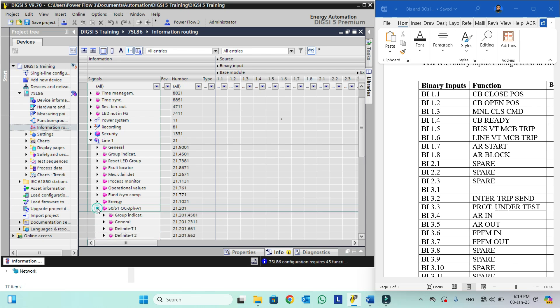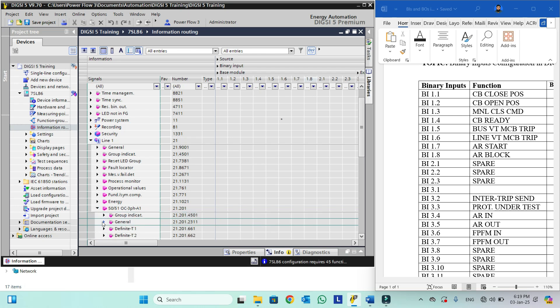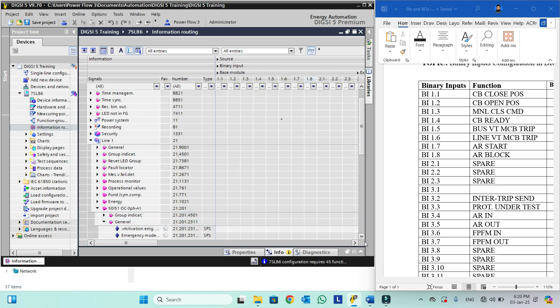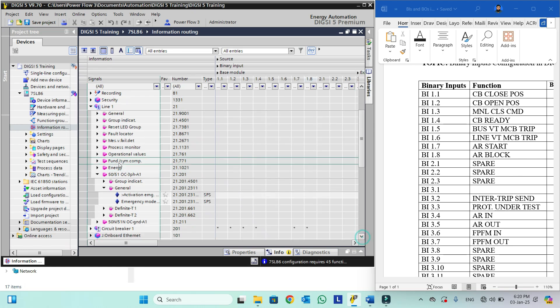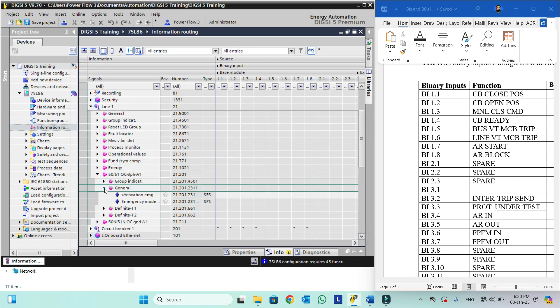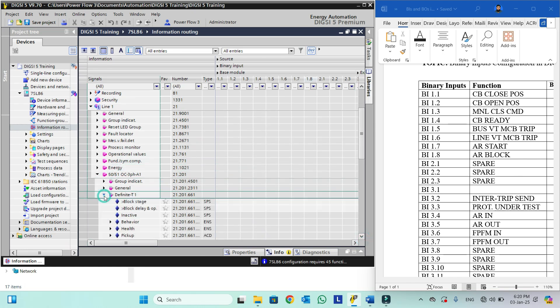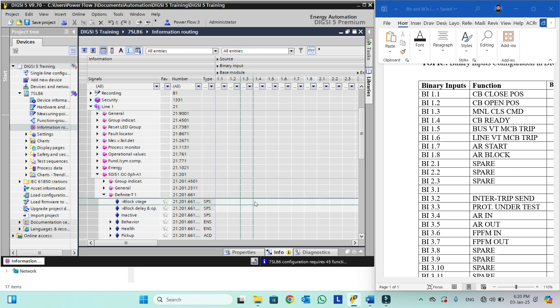For example, we can block this overcurrent function if we want. So we can block any function in the block stage. This protection under test feature is normally used for differential protection — we need to block the differential protection if it is under test so that it should not operate.